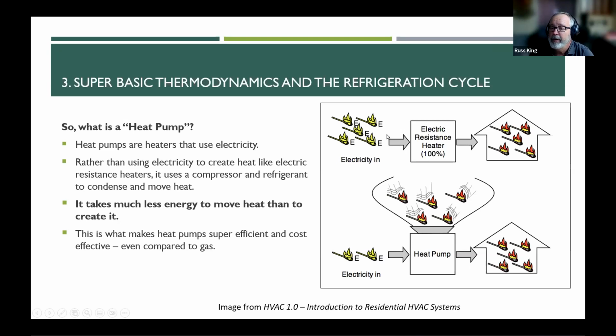In this diagram, you've got 5 BTUs worth of electricity going into an electric heater, and you get 5 BTUs out of it. That's 100% efficient. But with a heat pump, you put 2 units of electricity in and it finds 5 BTUs of heat in the air. So it's only taking 2 BTUs worth of electricity to move 5 BTUs. It's kind of like creating them, but it's really stealing them from somewhere else. We don't care where they come from, generally speaking. Now, we are making the outside air a little bit colder, but not noticeably so. And that's why they're so efficient. They're moving heat from one place to the other. They're using BTUs that already exist, and it takes a lot less electricity to move heat than it does to create heat.